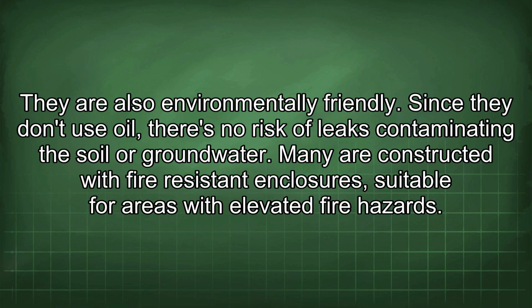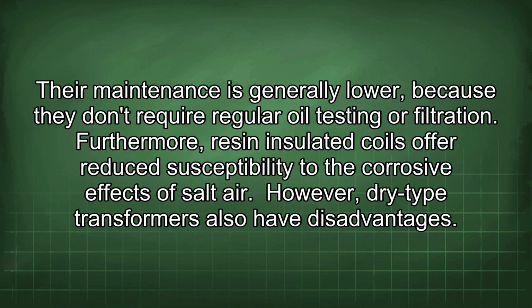They are also environmentally friendly. Since they don't use oil, there's no risk of leaks contaminating the soil or groundwater. Many are constructed with fire-resistant enclosures, suitable for areas with elevated fire hazards. Their maintenance is generally lower, because they don't require regular oil testing or filtration. Furthermore, resin-insulated coils offer reduced susceptibility to the corrosive effects of salt air.